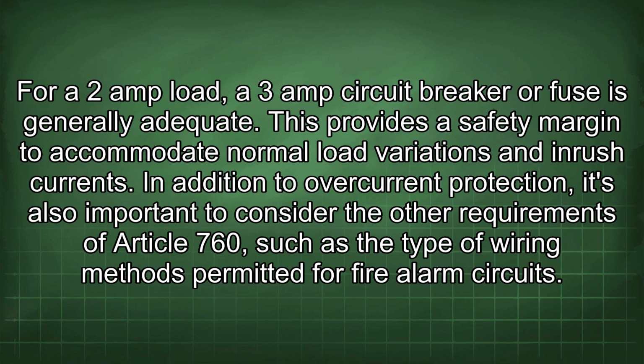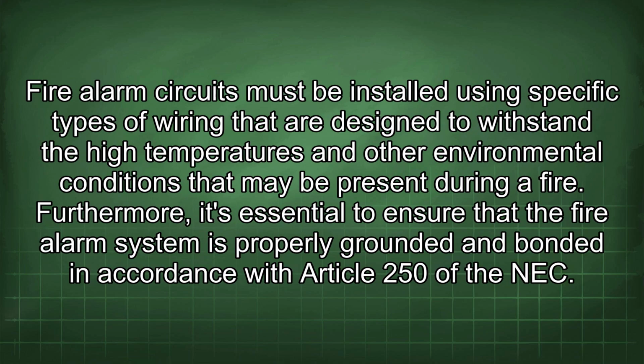In addition to overcurrent protection, it's also important to consider the other requirements of Article 760, such as the type of wiring methods permitted for fire alarm circuits. Fire alarm circuits must be installed using specific types of wiring that are designed to withstand the high temperatures and other environmental conditions that may be present during a fire. Furthermore, it's essential to ensure that the fire alarm system is properly grounded and bonded in accordance with Article 250 of the NEC.